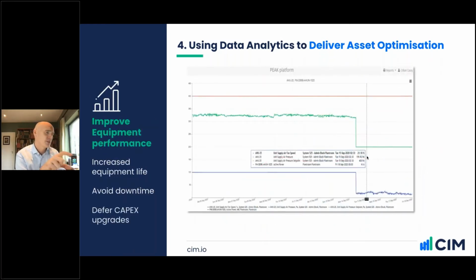And here's another example, this one around equipment, improving the life cycle of equipment. It's just a quick example, but it shows an air handling unit that had a static air pressure set point that it could not achieve. And you can see here that the supply fan, this is the blue line at the bottom, was running at 100%, the VSD was running at 100%.